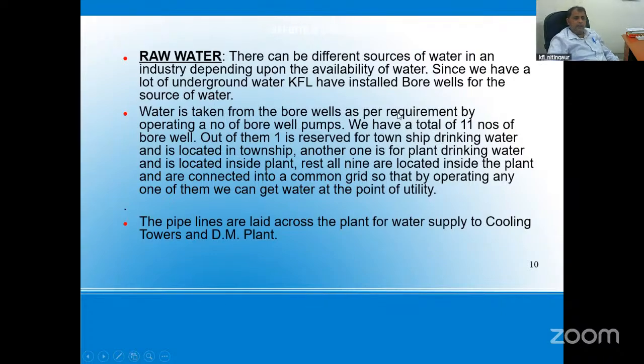Raw water has a number of impurities inside it. Minerals are also available in the raw water, which cannot be directly used to run the steam boiler. Why? Because these minerals in the raw water create a layer inside the tubes of the boiler. Our plant has water tube boilers. It means water inside the tubes and heat source outside the tubes.